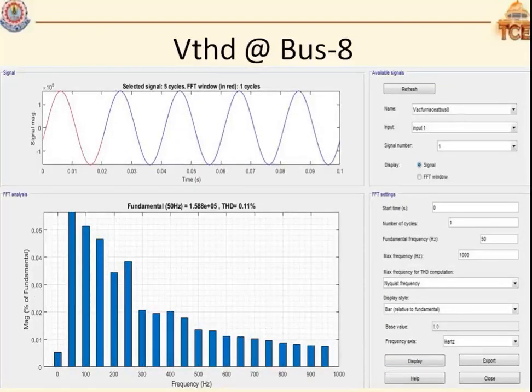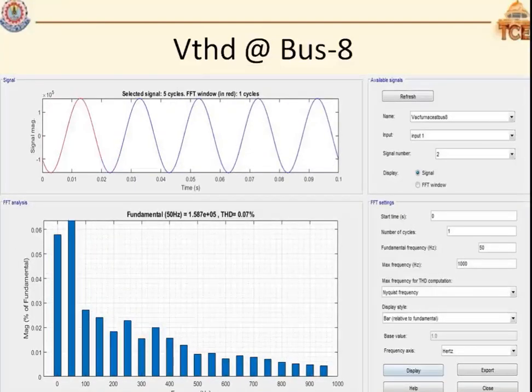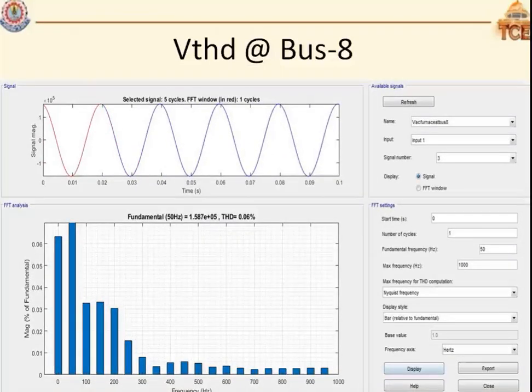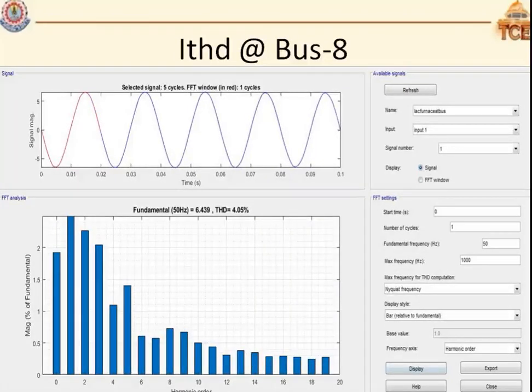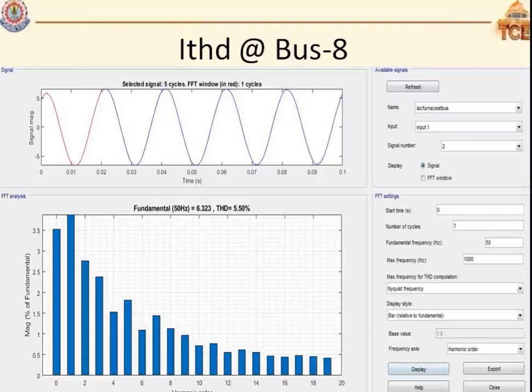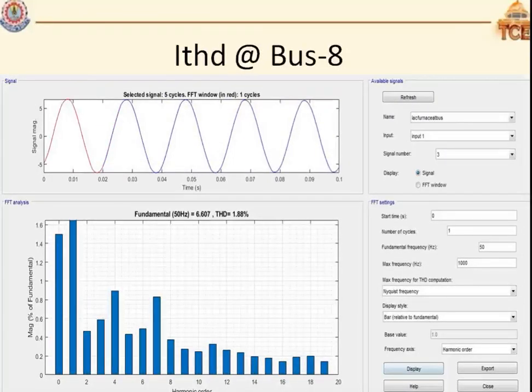It is the adjacent bus, where the measured voltage THD is 0.1%. It is a little amount because the transmission line is modeled as a nominal pi model. In the nominal pi model there are two shunt admittances, which are capacitances connected in shunt. And this is the current THD, which is about 4%, and for another phase 5%, another 1.88%. You can see how many orders of harmonics are present. Odd order and even order harmonics are all present. We cannot predict which order of harmonics will be present in the grid.